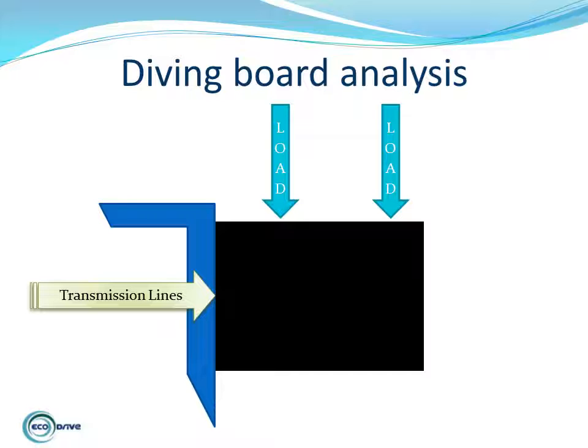To limit the power loss, transmission voltage is stepped up, such as at Gladstone, where the main feeder heading south is at 250,000 volts. Stepping the voltage up lowers line current and hence resistive power loss, but it does increase tracking and corona discharge, as is currently being experienced between Perth and Kalbarri. The starting of heavy loads connected to long transmission distribution networks may cause voltage sags and currents. There are a number of compensator arrangements installed at different locations, controlled to supplement the power quality conditions such as voltage sag, power factor, as well as overvoltage.